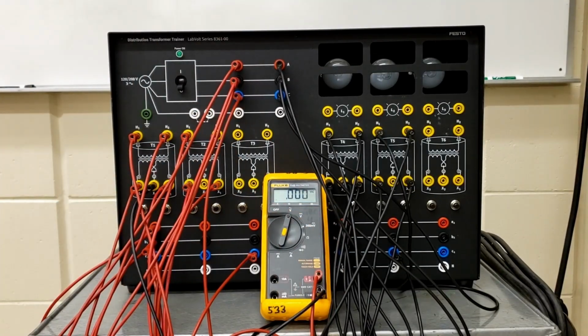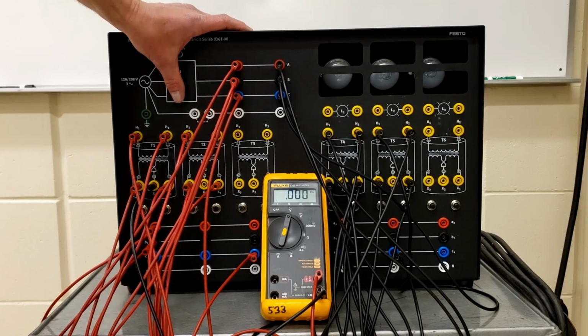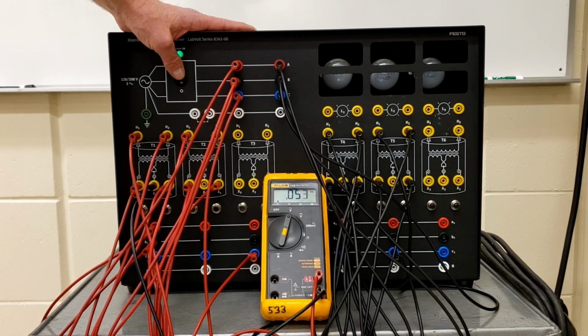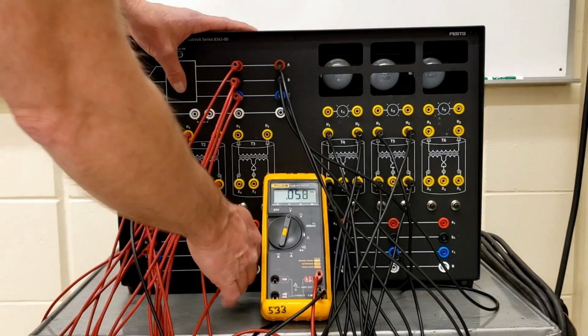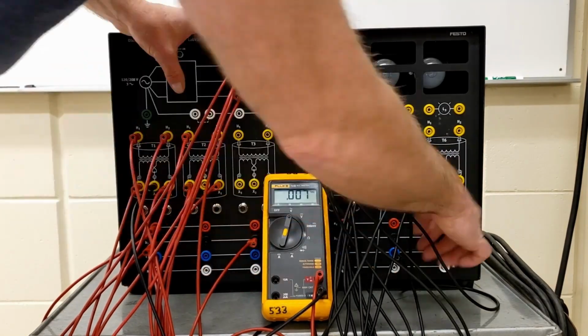Let's see if there's a glare on the image there. Nope, looks good. Okay, so let's see. We're now testing between the two C phases. There we go. So no voltage difference between those guys. Now that we have bonded the X2s together, transformer 1 and transformer 4.